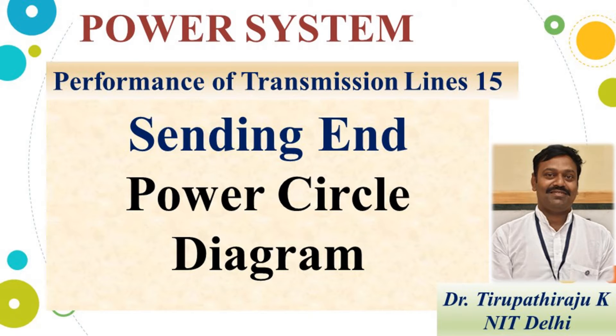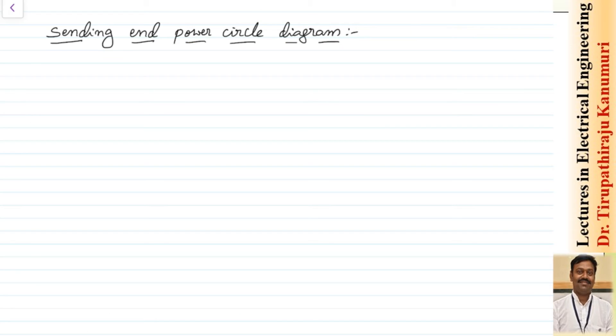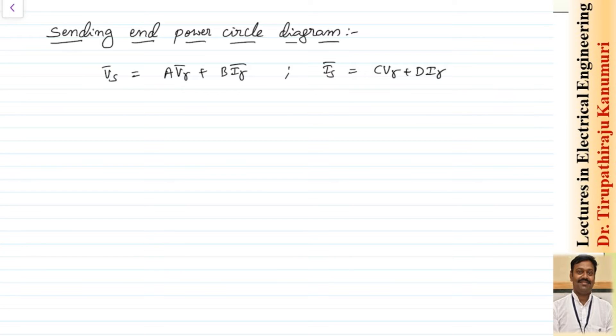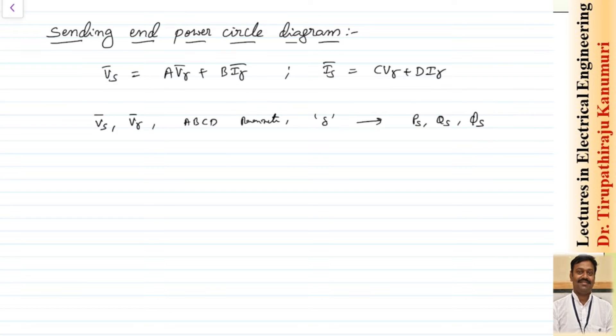Today we are going to discuss about the sending end power circle diagram. To calculate it, we know from the ABCD parameters that Vs equals A times Vr plus B times Ir, and Is equals C times Vr plus D times Ir. If we know the sending end voltage, receiving end voltage, ABCD parameters, and the load angle — the angle difference between Vs and Vr — we can easily calculate the sending end active and reactive powers as well as the sending end power factor.